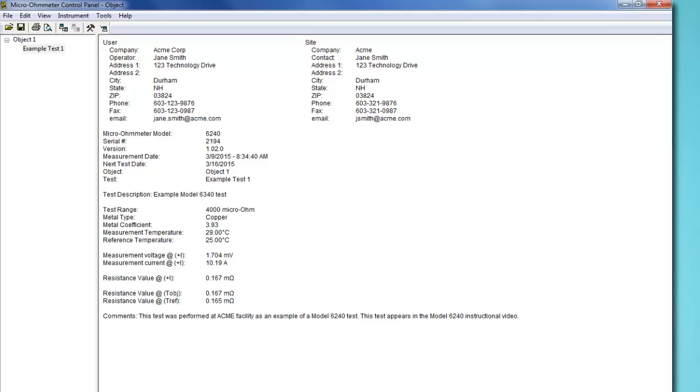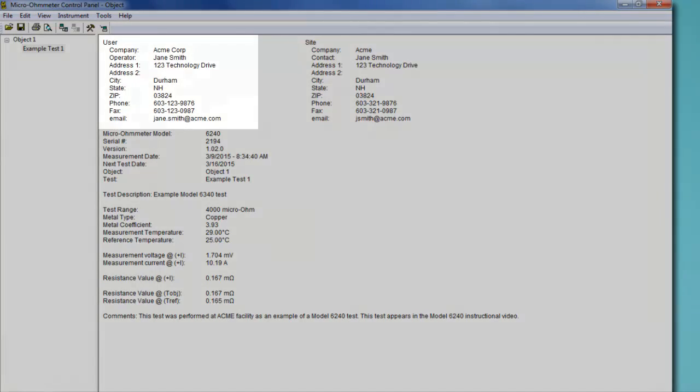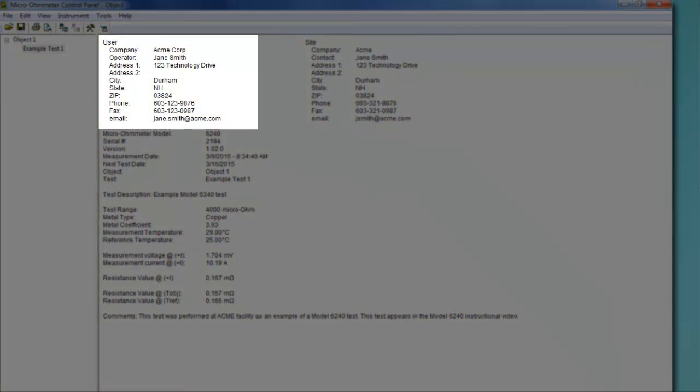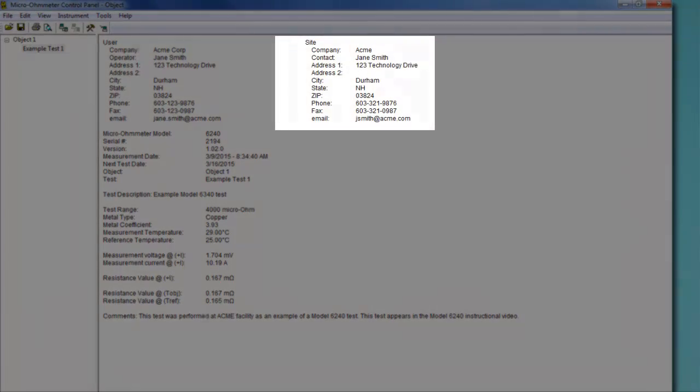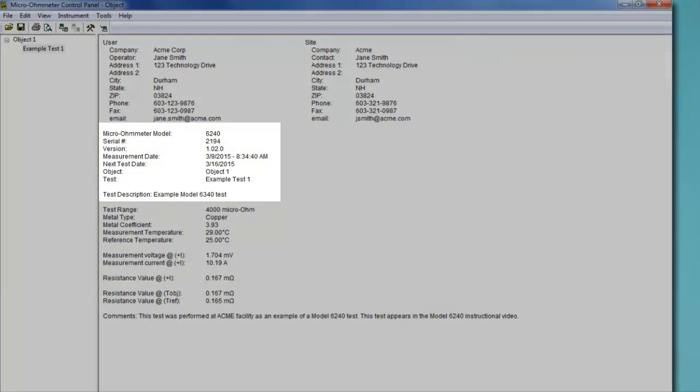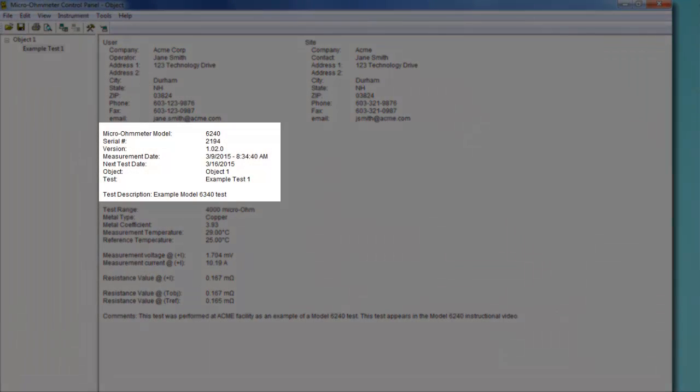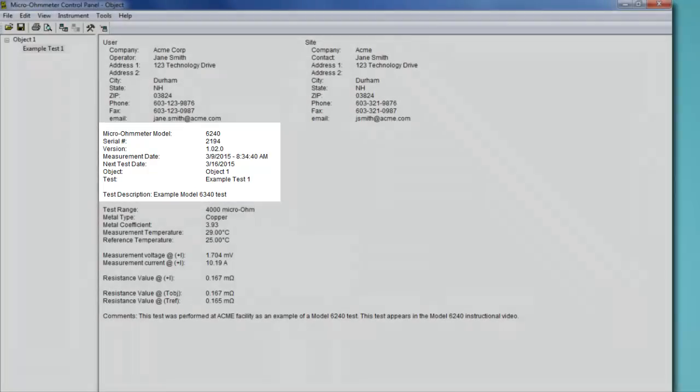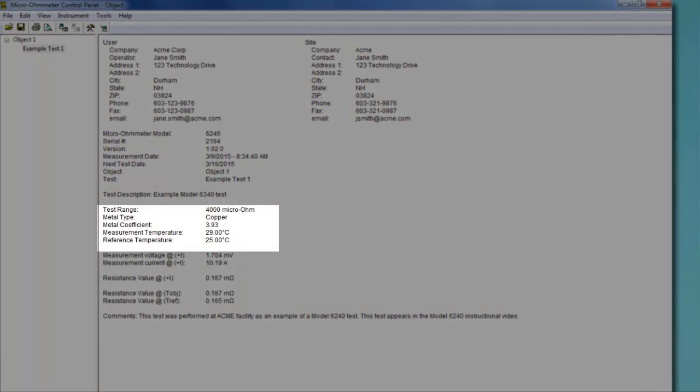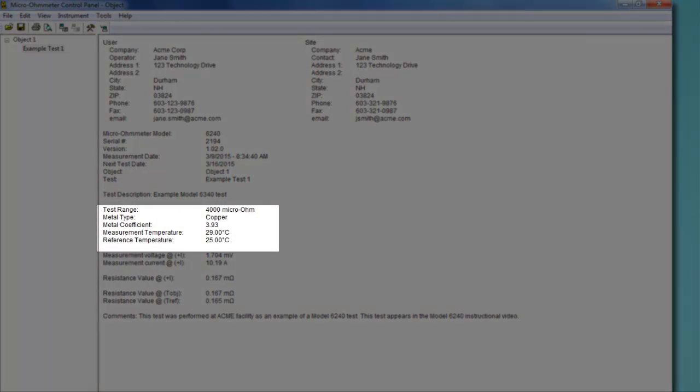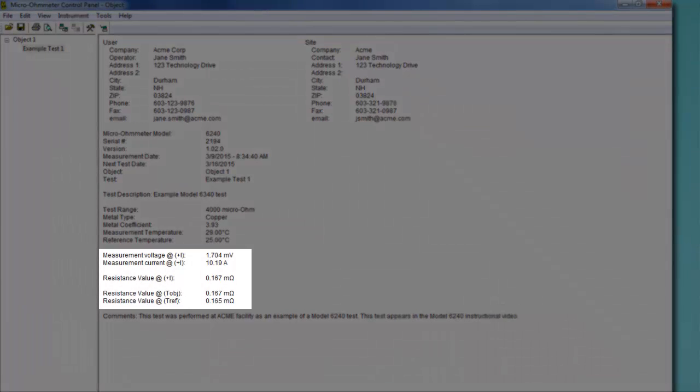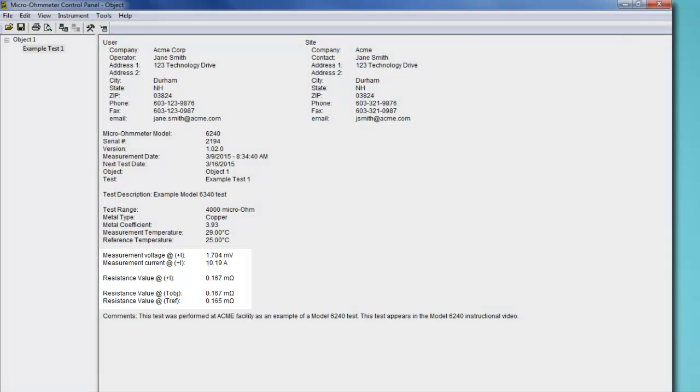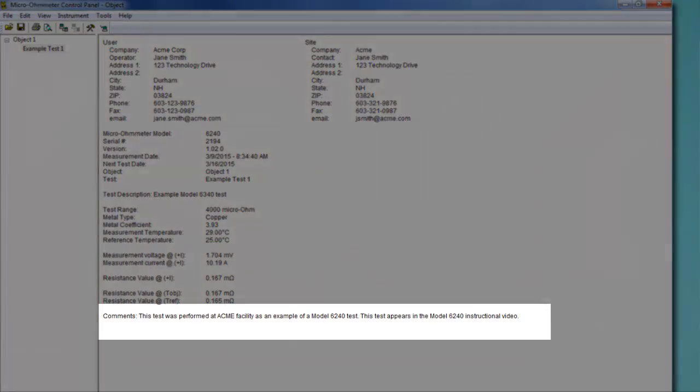You can now view the complete test record. This includes information about the test operator, the test site, the instrument model and other test-related information, data related to the temperature offset, the test measurement data itself as recorded on the Model 6240 instrument, and finally, any additional comments.